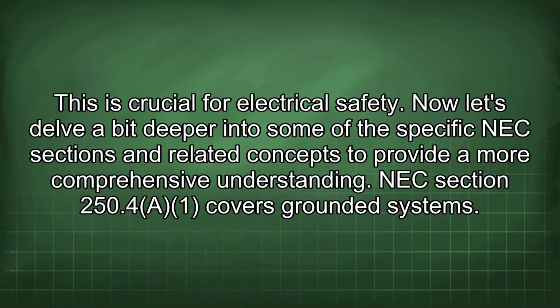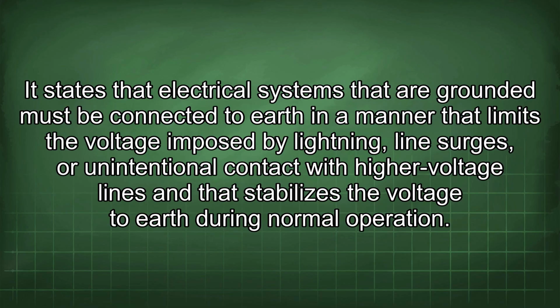Now let's delve a bit deeper into some of the specific NEC sections and related concepts to provide a more comprehensive understanding. NEC section 250.4(A) covers grounded systems. It states that electrical systems that are grounded must be connected to earth in a manner that limits the voltage imposed by lightning, line surges, or unintentional contact with higher voltage lines, and that stabilizes the voltage to earth during normal operation.